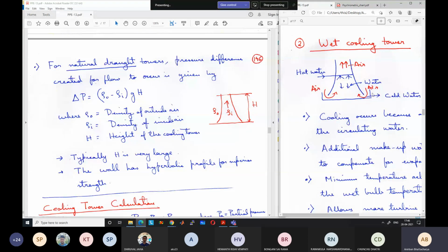of power. Okay. So remember that the cooling water which is being circulated, we will see in a problem today, is many times larger than the steam that is circulated in the power plant or the steam generator and turbine. Okay, so we will see in a problem today that if we are circulating 100 kg per second of steam, the cooling water required is around 6000-7000 kg. So 60-70 times mass flow rate of cooling water is required.